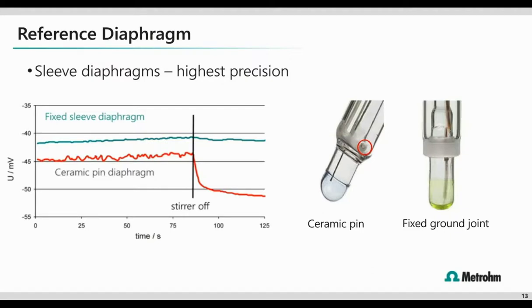When it comes to using them, the only difference you'll need to understand is the impact of stirring, and that's the graph on your screen. If we put both of these electrodes into a stirring sample and watch the signal, we see a fairly steady response, okay? Once we shut the stirring off, you can see the ground joint diaphragm maintains a steady signal while the ceramic pin starts to trail off.